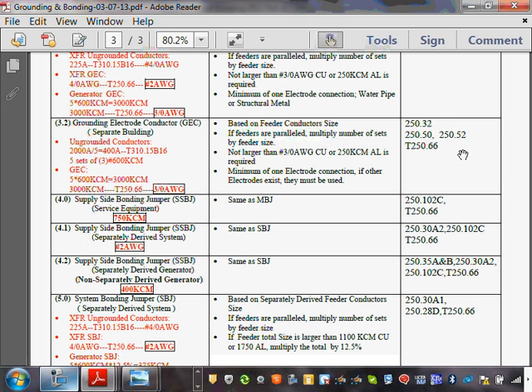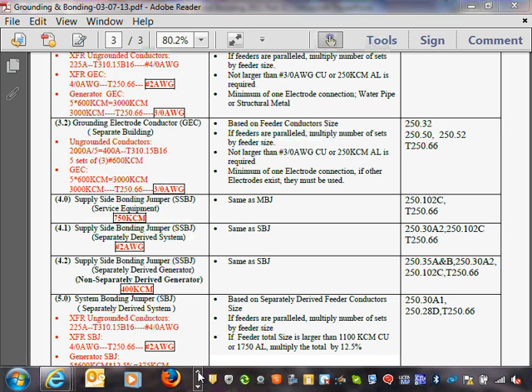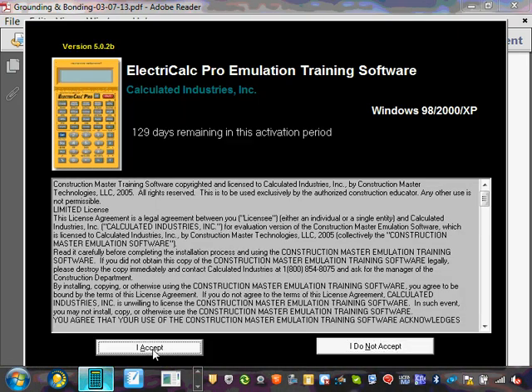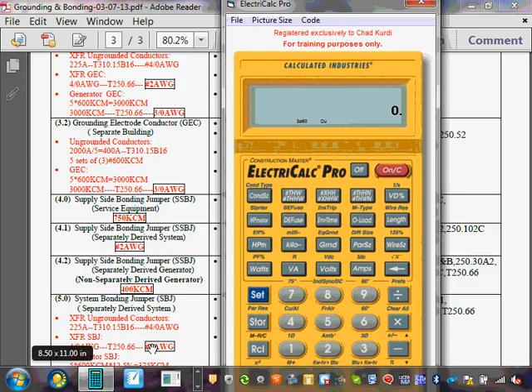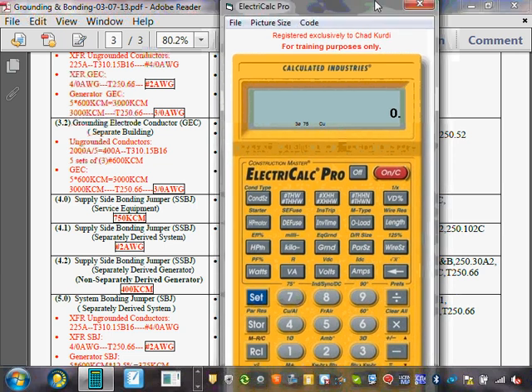Any comments, guys? Any questions? Equipment grounding conductor. What size equipment grounding conductor would we need for this? Okay, I'm going to impress you with that one, guys, and size it based on this. Shall we try it? Anybody want to size it? Here's a calculator that I told you about. Let's size the equipment grounding conductor on that. Set this one to 75. Okay, so my equipment grounding conductor.